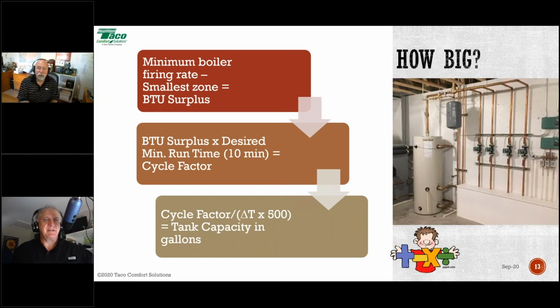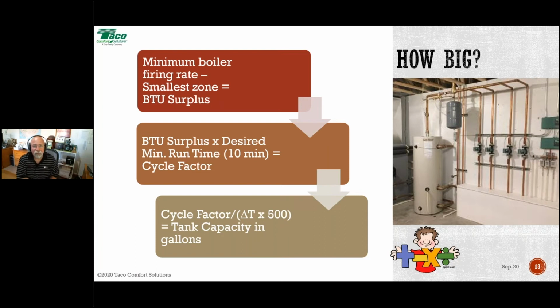Come back in, buddy. But in the meantime, I'll just go through this with you. Remember that when he's saying the minimum of the boiler, he's not talking about when you do 5-to-1 turn down or 10-to-1 turn down, right? You've got to figure out what that lowest possible firing rate is at full turn down of that particular boiler. And then you're doing the comparison between the two. What is the minimum load on a design day versus that lowest turn down setting that the boiler can offer as well? So that's what we do with that.